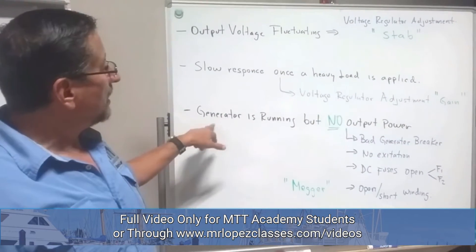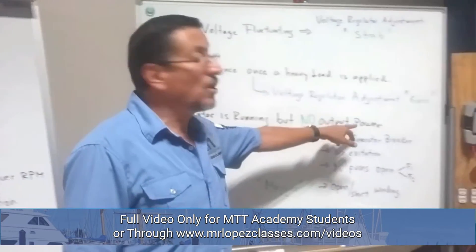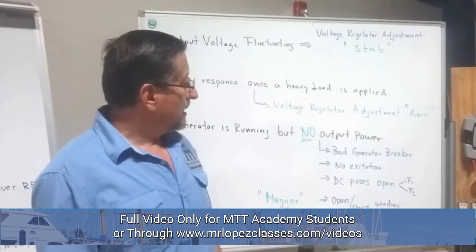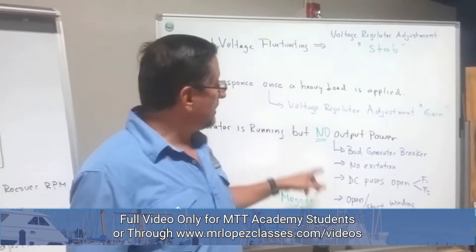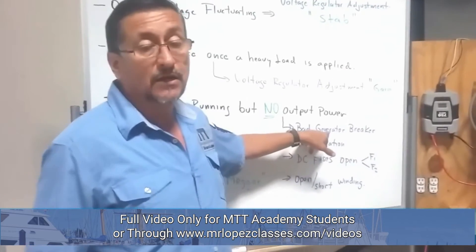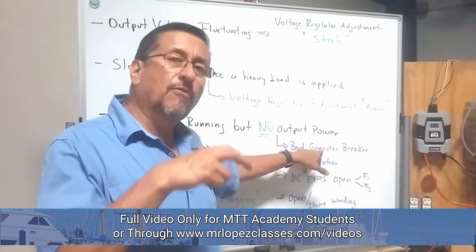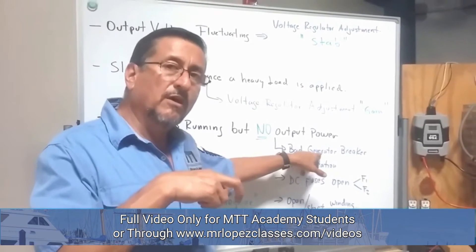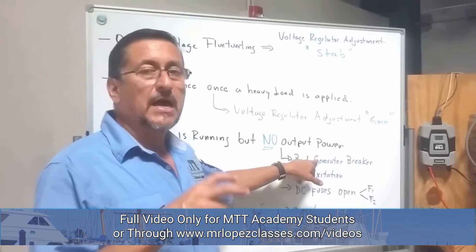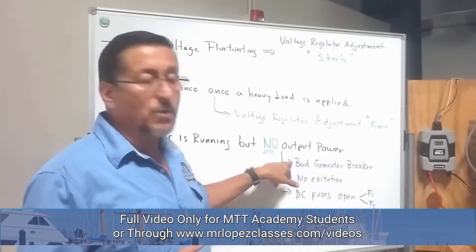The last issue is when the generator is running but there is no output power. The most common possibility is that the breaker on the generator is bad. You need to verify the voltage at the input of the breaker. If the voltage at the input of the breaker is good and there is nothing at the output, the breaker is probably broken.